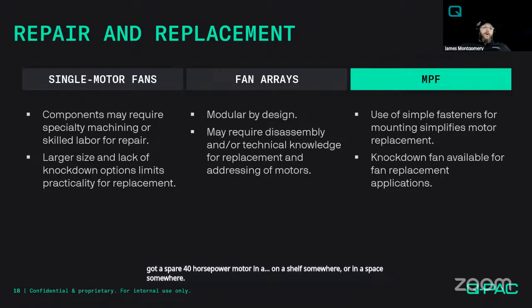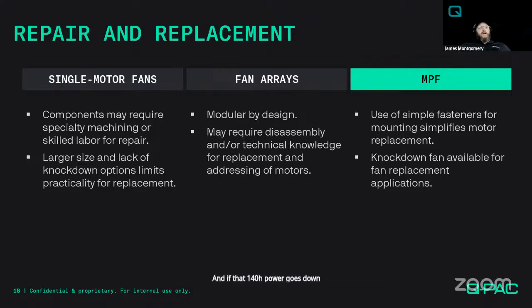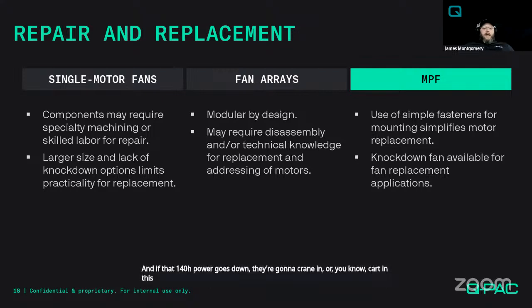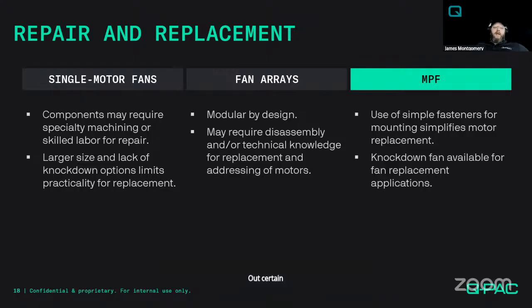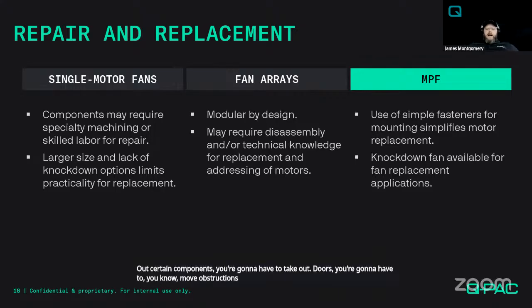And if that one 40 horsepower goes down, they're going to crane in or cart in this large AC motor. And in order to do something like that, a lot of times that's not going to fit through the opening of an air handler. So you're going to have to knock out certain components. You're going to have to take out doors. You're going to have to move obstructions and stuff.